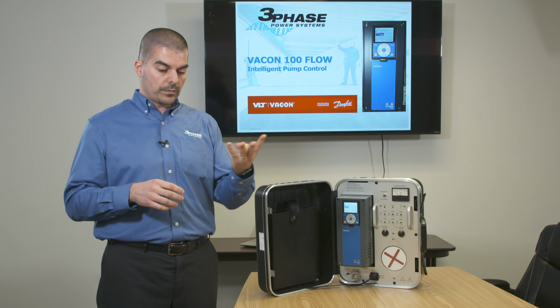We can also monitor the power on time. So a lot of other drives that have external meters, timers, and selector switches, now all of that has been eliminated because everything can be monitored from the keypad. Now here is this example of the power on time. And if we want to flush the lines, we can also monitor that. Now, this is just an example. This is the tip of the iceberg of what is capable to be achieved with this unbelievable drive.